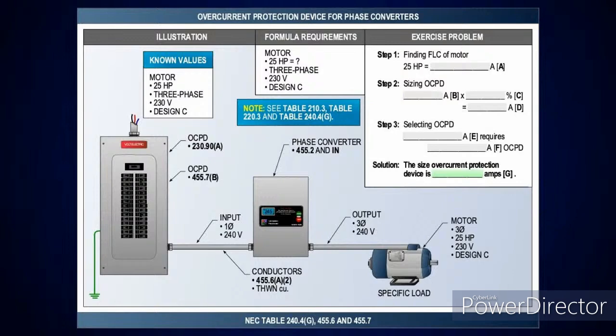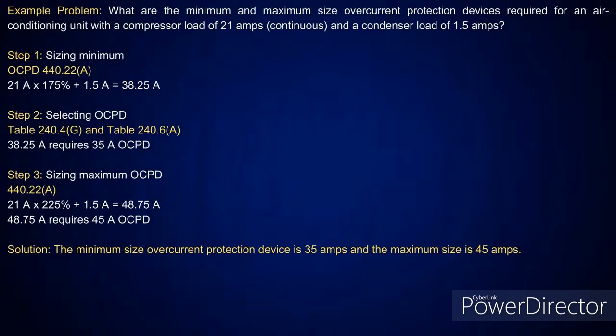And that's why we go through this over and over and over. It's almost like repetition, but it's different items. But I'm really never changing anything. It's just what I need for this, what I need for this. And I'm still applying the same type of calculations. And I'll tell you one of the things that's very interesting about this. If you ever notice, pretty much everything I start off with is getting what? The amperage. Even when I size my transformer, get the amperage. Once I get the amperage, then I'm looking for what? Percentage. That's pretty much the way you do everything.